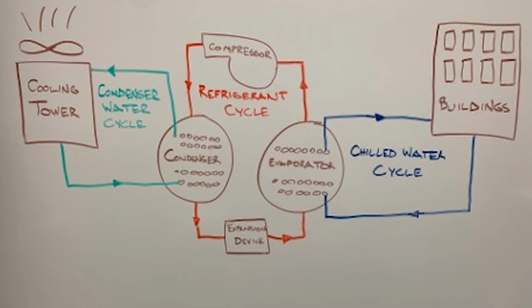The diagram shown here was drawn by Lee Baker, the chilled water systems manager. Starting at the cooling of the buildings on campus, chilled water cools the outside air that is distributed throughout the building. This chilled water then needs to be recooled and will make its way back to the chiller water utility plant. Here, we move to the 3 cycles of the chilled water process. First, refrigerant absorbs heat from the chilled water, thereby cooling it again for redistribution to the building. Condenser water then cools the now warm refrigerant. Finally, the warm condenser water is pumped to the cooling tower and cooled by air through evaporation.